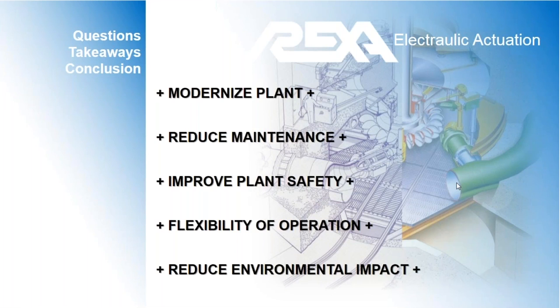The worry we had about fail-safe, if let's say the unit quits functioning, really is not much of a worry at all. It could fail-safe in a locked position, it could run shut, it could run open, but we chose to just lock the needle in place in case the controls quit functioning or there is loss of signal. Anyway, there's probably plenty more you may want to ask. I will leave it at that, and let's see what questions come.